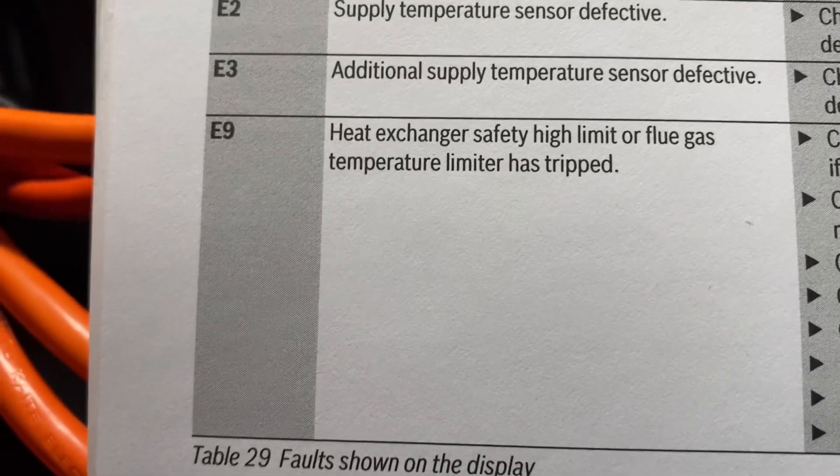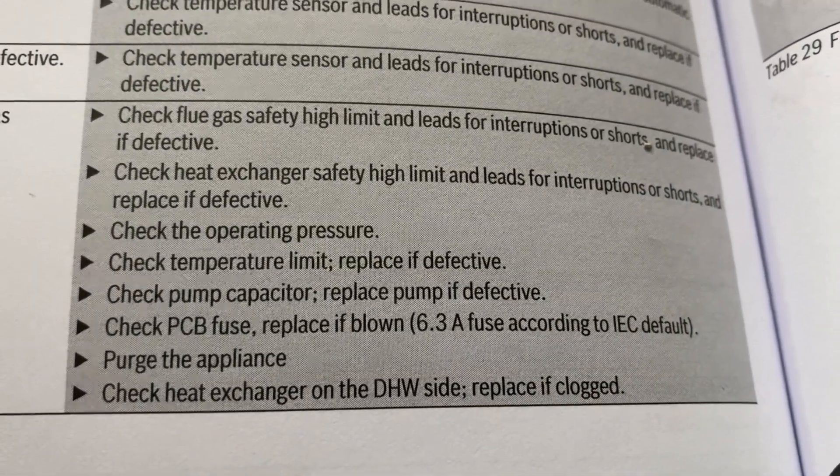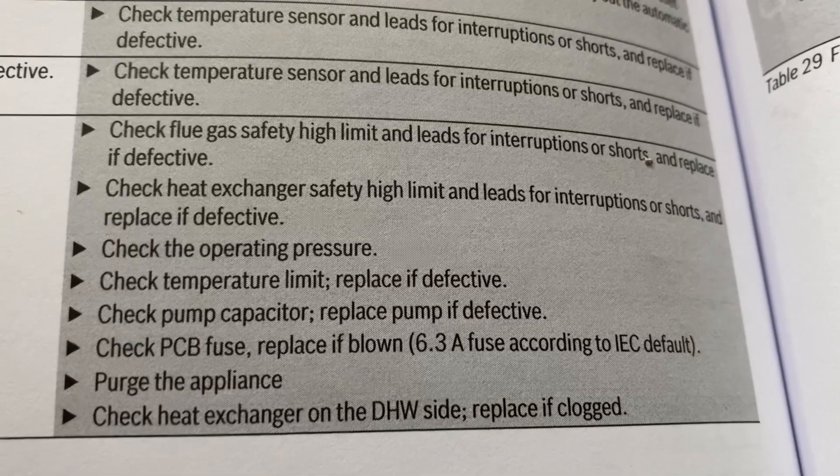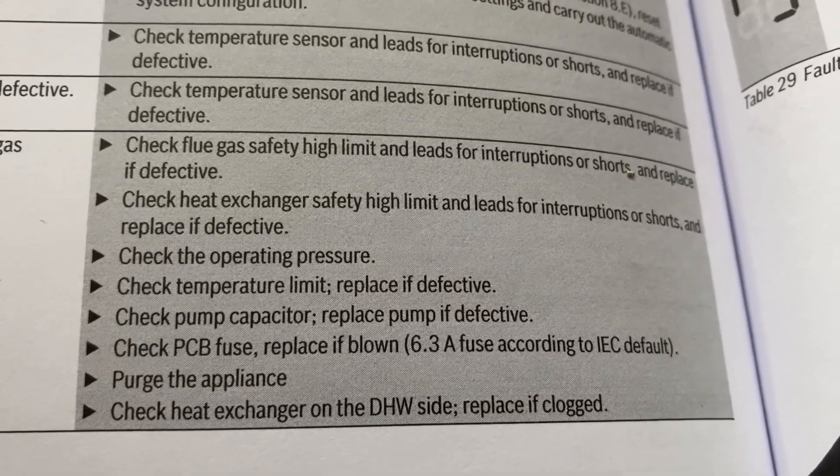Let's review E9 — page 74 of the manual. Fault E9: heat exchanger safety limit or flue gas temperature sensor. The temperature limiter has tripped. Those are the listed options. Press pause. All right — on none of these steps does it tell you to check those two screws.